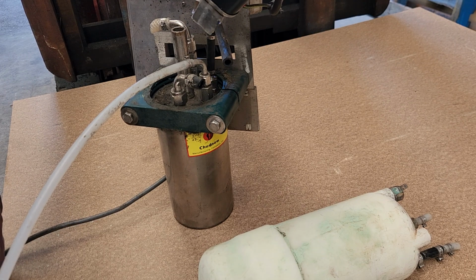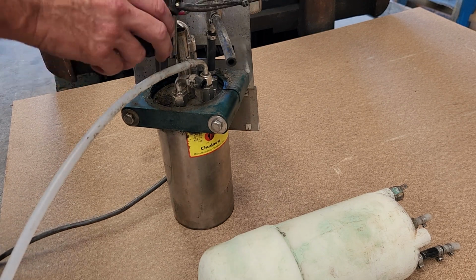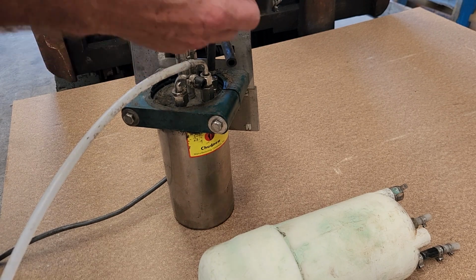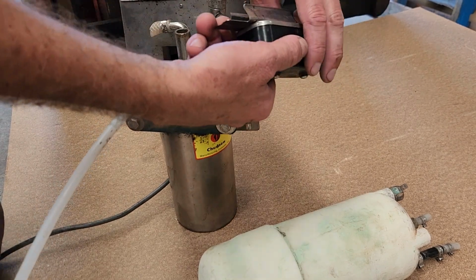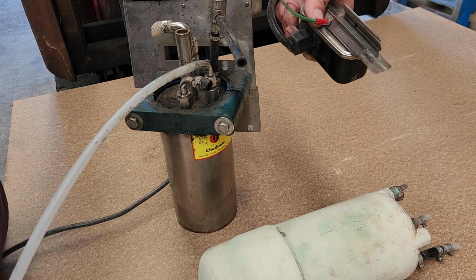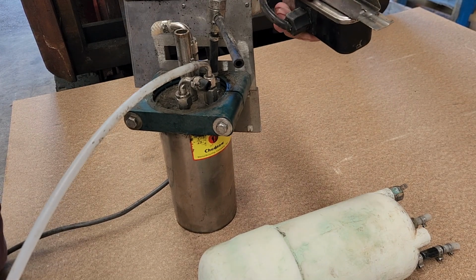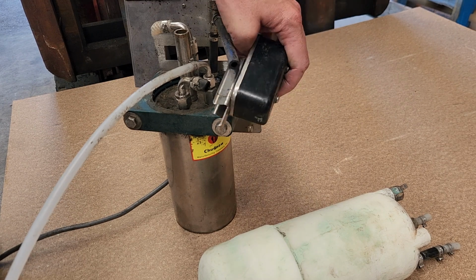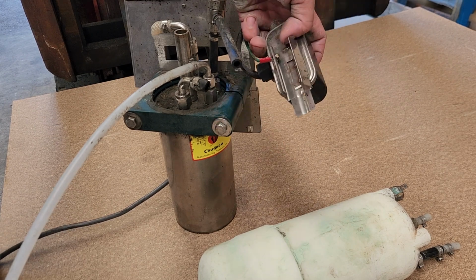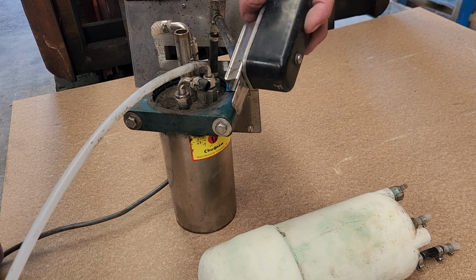Now, a couple of things can go wrong with this one. First of all, it's all magnetic. It can get stuck. So if your motor's continuously running, take this off, give it a shake. You can actually hear it moving. Turn it one way, the motor should turn off. Turn it the other way, the motor should turn on. So, make sure that happens and watch the motor turn on and off.